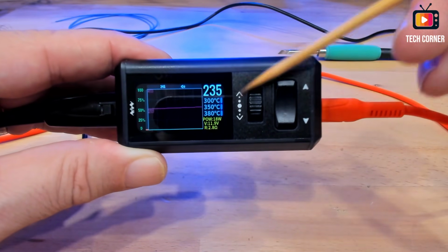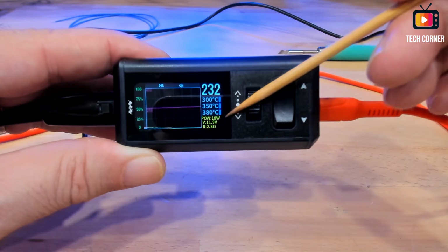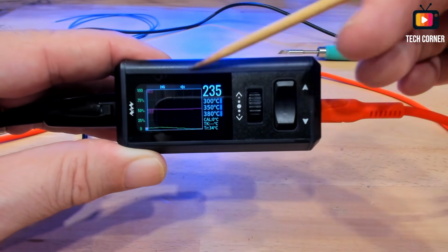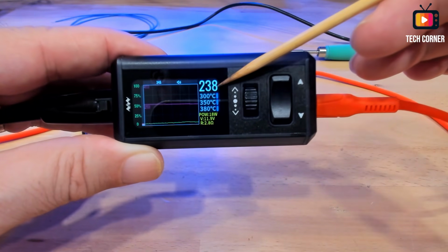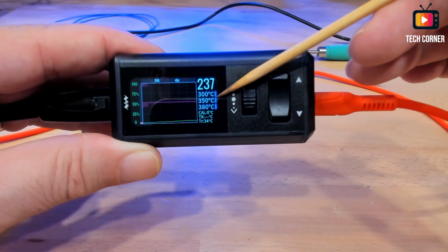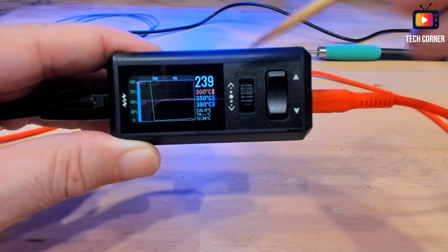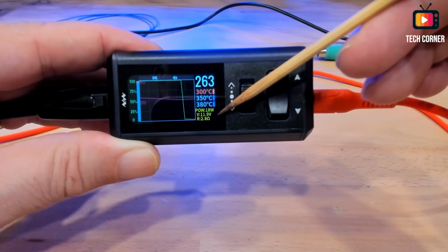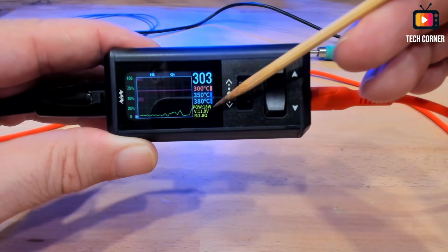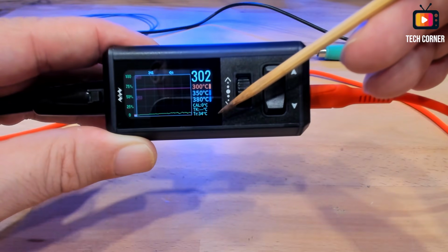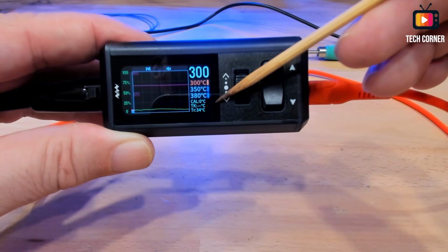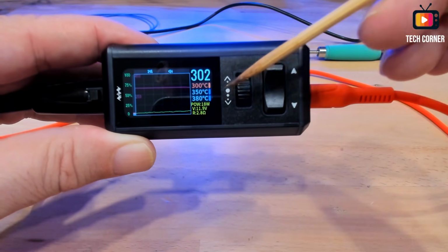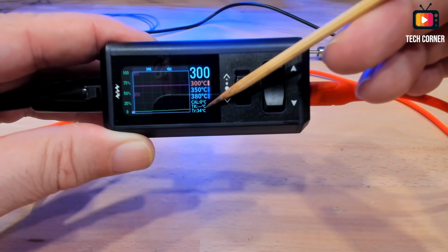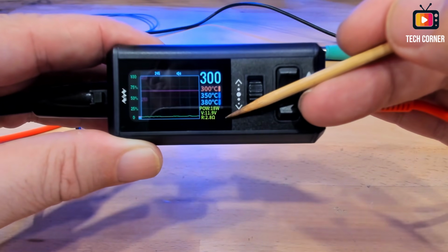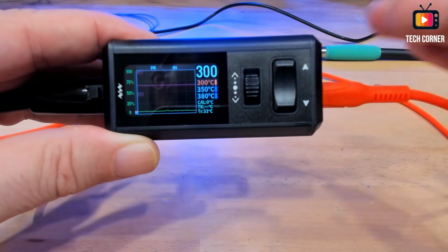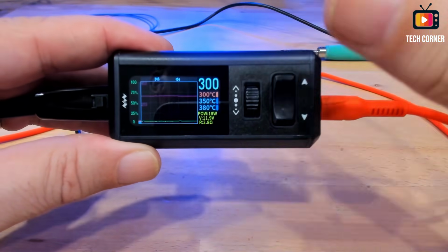Another menu that is also available, I think that we can see it by pressing here, is this waveform of the temperature. The options on the right are basically a condensed form of what you had in the previous menu. You have here the tip, the sound indicator, the current temperature, and the preset selection. We don't have any preset selection right now, but if we select one, it will be on red, just like the previous menu, changing here in the bottom with values. So those are the values of the energy in yellow, like the power, voltage and resistance, and then you have for calibration the different temperature, like we saw on the menu to set. This is the probe temperature, and the TR is the cold end reference point temperature, so it seems to be the temperature that serves as reference when the tip is cold.